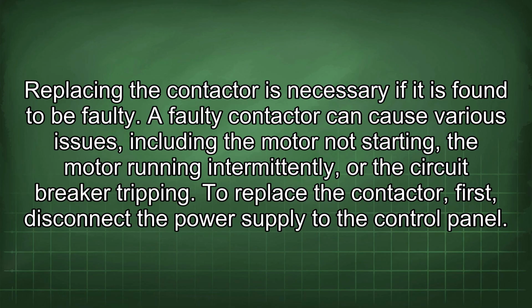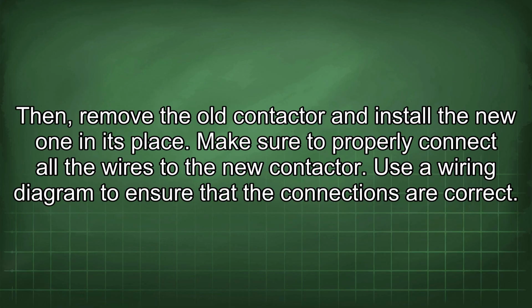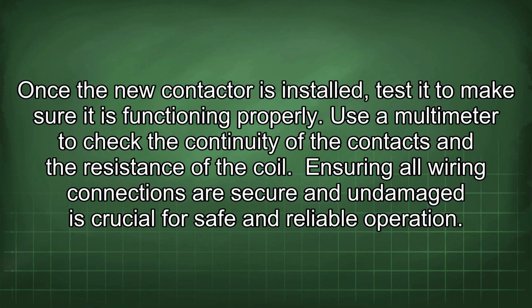Replacing the contactor is necessary if it is found to be faulty. A faulty contactor can cause various issues, including the motor not starting, the motor running intermittently, or the circuit breaker tripping. To replace the contactor, first disconnect the power supply to the control panel. Then remove the old contactor and install the new one in its place. Make sure to properly connect all the wires to the new contactor. Use a wiring diagram to ensure that the connections are correct. Once the new contactor is installed, test it to make sure it is functioning properly. Use a multimeter to check the continuity of the contacts and the resistance of the coil.